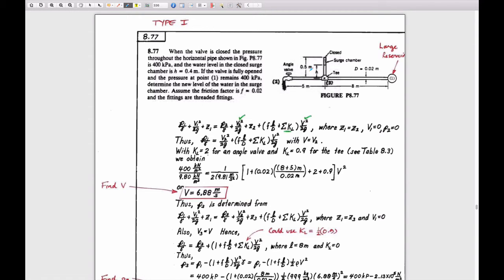So it happens to be something that's in a piece of fabricated pipe, but it also exists in other systems, and for the same reason. So that when you shut this valve off here, the water that's charging down here, or the fuel oil that's charging down here, instead of busting this valve off, it actually has somewhere to dissipate its energy into the system.